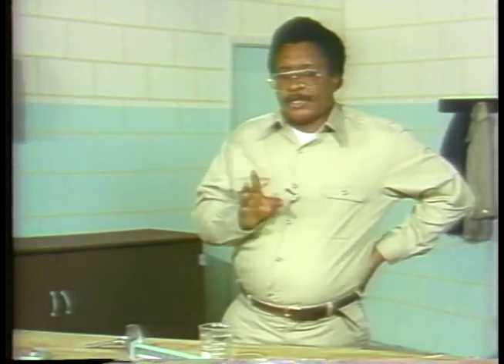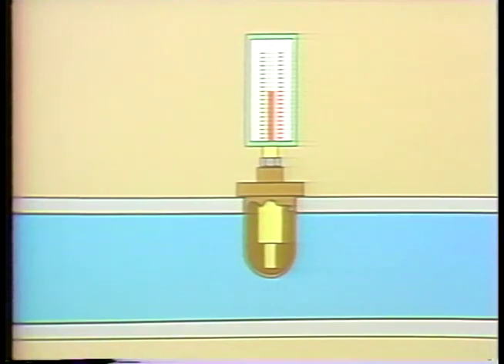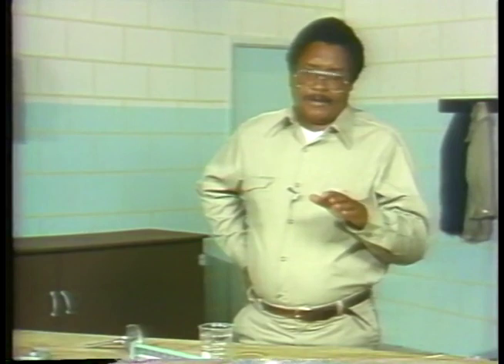However, there are situations where this procedure doesn't work well. If the material is highly corrosive or under a great deal of pressure, the sensing element could be damaged. To prevent this, thermowells can be used. A thermowell is a recessed opening that protrudes into the component where temperature measurements are taken. In this example installed in a pipe, the thermowell extends into the path of the fluid and is usually about the same temperature as the fluid. If temperature fluctuates, there may be a time delay before the thermowell reaches the same temperature as the fluid — this is one of the disadvantages of thermowells.